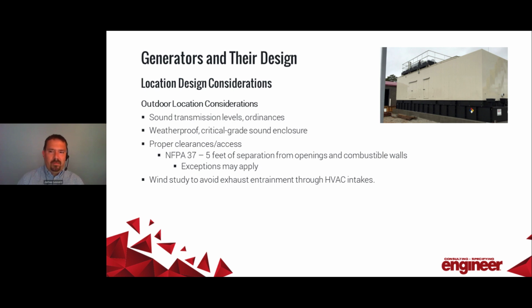So if you're outside, NFPA 37, which is the standard that deals with the prime mover portion, the engine portion of the generator, has something to say about getting access and avoiding being too close to the building or combustible materials. It requires a 5-foot separation between the prime mover and openings of the building, such as doors or windows, and combustible wall materials. There are some exceptions. So if you're looking to do something a bit outside the box, it's probably best to consult the exceptions and see if there's something that you can apply there.